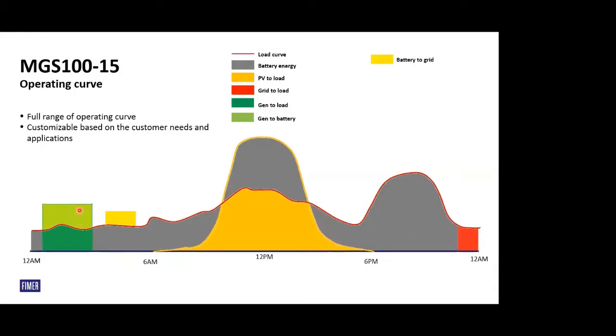And if the grid needs power because there is a shortage of power in an adjacent village, we will be able to do so by transferring power from the stored energy of the batteries into the grid, so that it can be used for the adjacent village. Then of course, if there is a grid available and the batteries are already fully charged in the afternoon, we can also choose to export to the grid. When we integrate a biomass or wind generator, it can augment a certain portion of the load, and the rest will again be catered by the PV if PV is available, or the batteries will always kick in to deliver the deficit power whenever required.